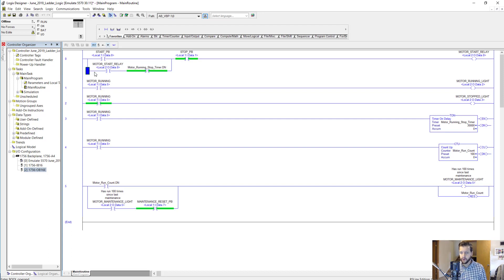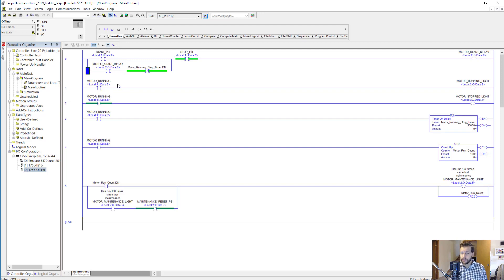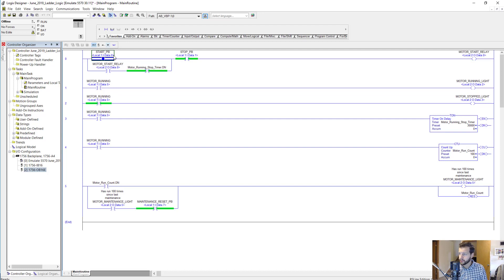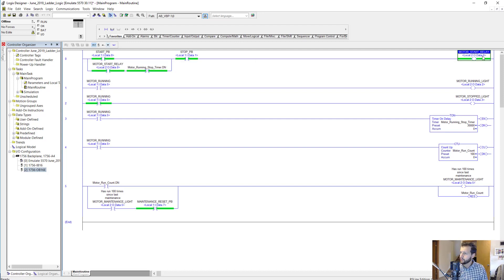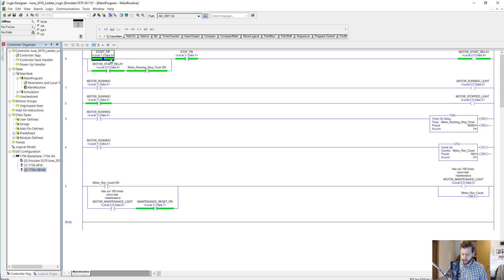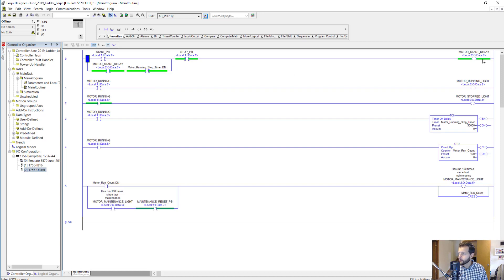This is what is called a seal-in or latching ladder circuit. So this part of the logic won't engage until we first engage the output with the upper part of the circuit. When this part of the circuit becomes true, it turns on the motor start relay, which I'll just toggle to show you what that would look like. You can see that automatically turns on the motor start relay. Even when we turn this off, we have a path all the way to the motor start relay.